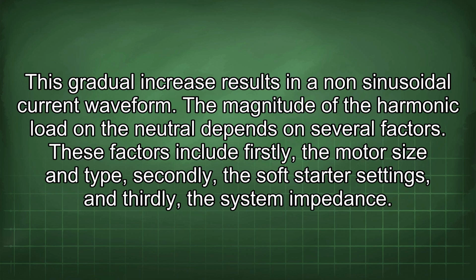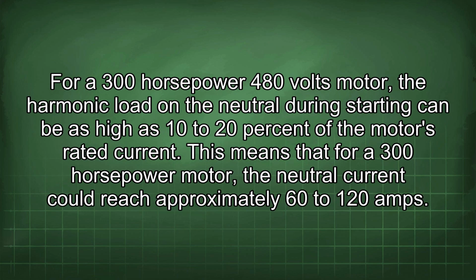The magnitude of the harmonic load on the neutral depends on several factors. These factors include, firstly, the motor size and type, secondly, the soft starter settings, and thirdly, the system impedance. For a 300 horsepower 480 volts motor, the harmonic load on the neutral during starting can be as high as 10 to 20% of the motor's rated current. This means that for a 300 horsepower motor, the neutral current could reach approximately 60 to 120 amps.